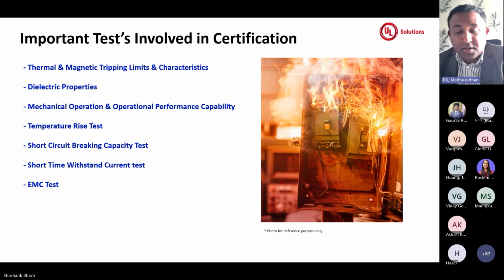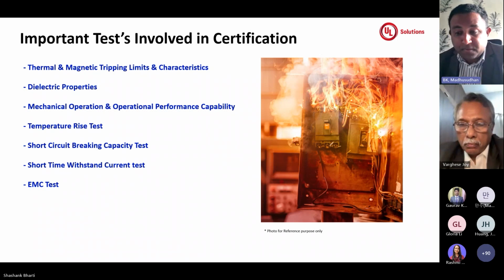So these will be looked in, and only if the ground fuses are intact are the results acceptable. If there is any blow of these fuses, this will be considered a failure, because the product has undergone arcing, and arcing has led the current to flow to the fuse, and the fuse will blow. So these are the major criteria that come up from the testing for breakers here. And also, if the breakers are declared for electronic types, then they will undergo an additional EMC test based on the requirements coming from the standard.